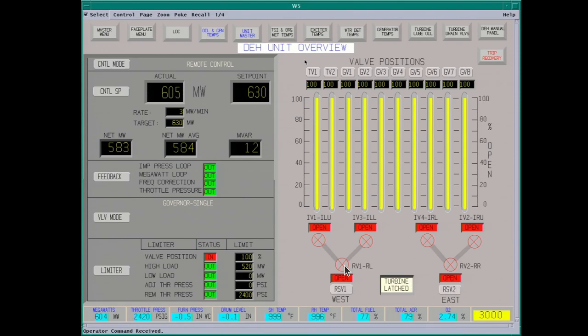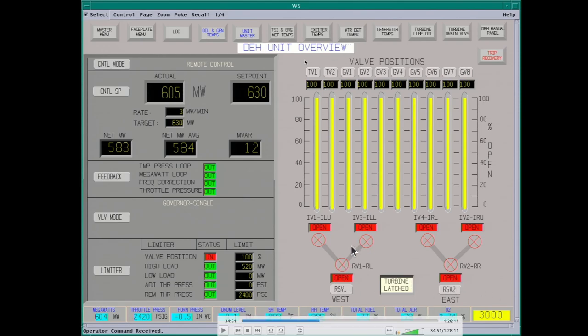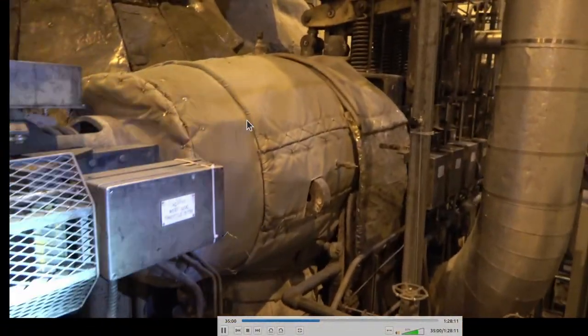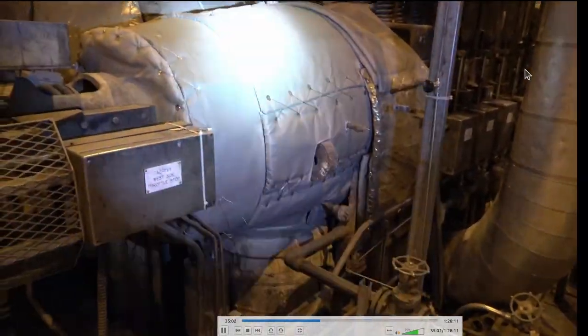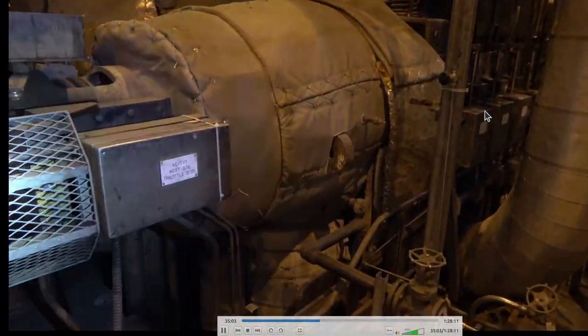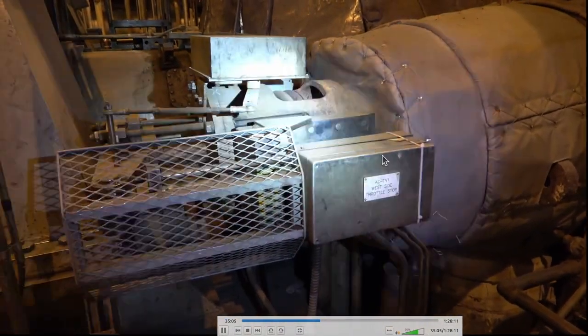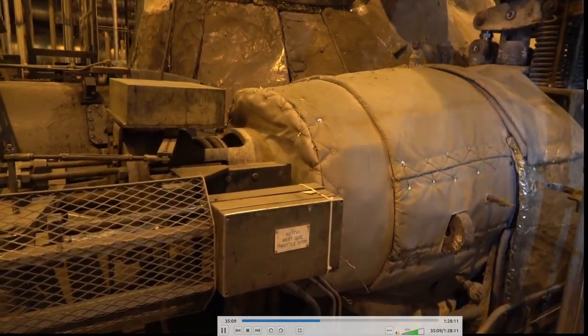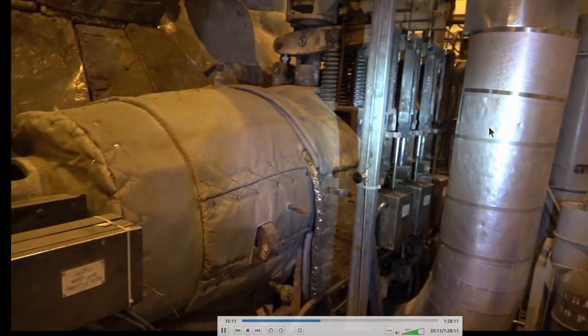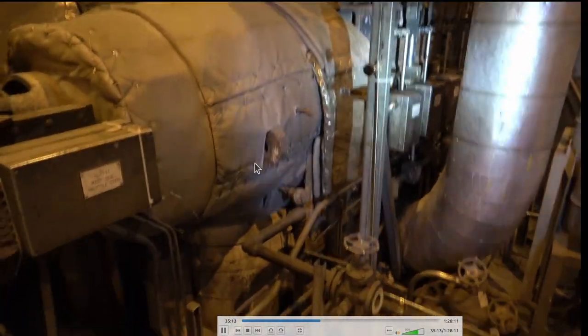This is the throttle valve — your governor valve sits right back here, there are eight of them. They have a little Moog controller inside that adjusts them. They're very accurate valves and these things shut in milliseconds. If there's a trip, the higher spring pressure will slam them shut.